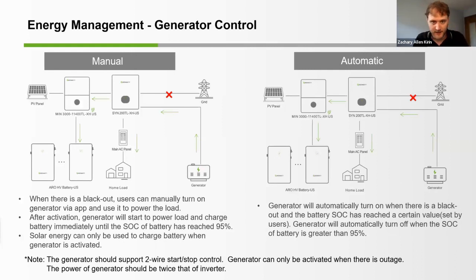Again, this is just a recommendation from our end, but the generator can only be activated when there is an outage, but the power of the generator should be about twice that of the inverter. The reason for this is we want to charge the battery and also supply the main AC panel with energy. So we're trying to supply the load as well as the battery charging. It doesn't have to be sized this way. This is the most ideal application. This allows the generator to charge the battery, power the home loads, everybody's happy.